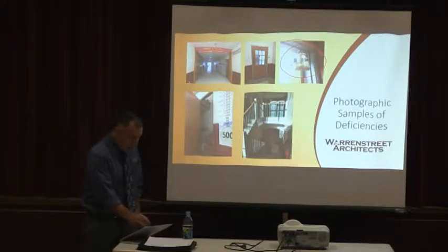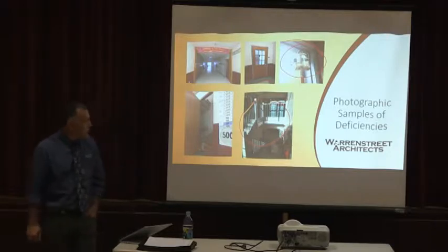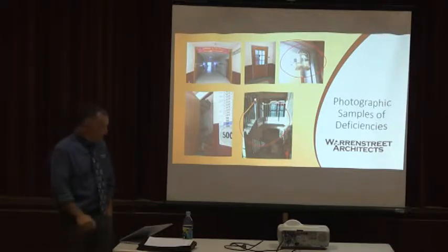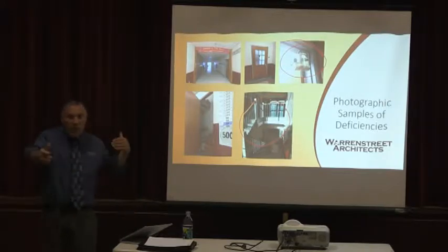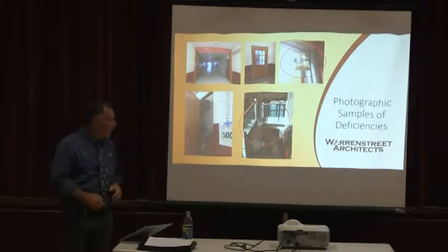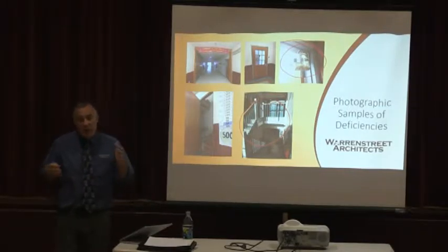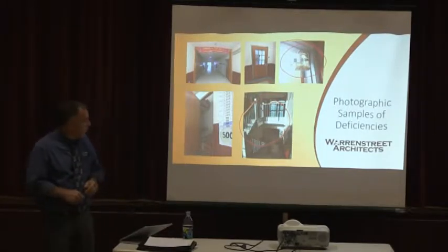The stairways have some issues in terms of the height and width. And then this one in particular: there's a number of spaces in the corridor that were wider when it was originally built, and over time it seemed to make some sense to utilize those little nooks for some storage. The problem is that they're open to the corridor, so you have flammable materials being stored in the storage room that has no fire rating to the corridor. And that's a serious deficiency in the code.